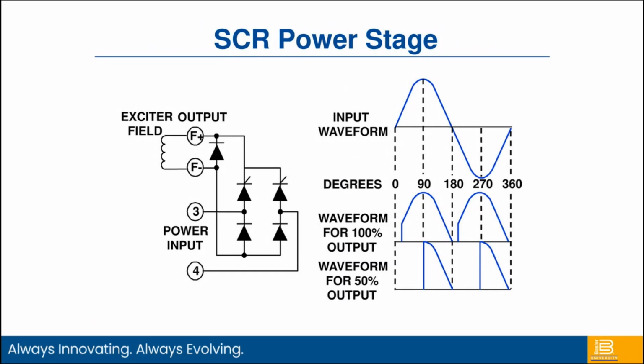At a high level, there are two different ways that we do this. We take that AC signal and we use silicon controlled rectifiers, or SCRs. In this case, we've got a full wave bridge. In other words, we are rectifying both the negative side of the AC waveform as well as the positive side, and we're going to gate that on through the SCRs. Our gating signal out of our controls will tell the SCRs how much of that AC waveform we're going to allow through, or rectify.